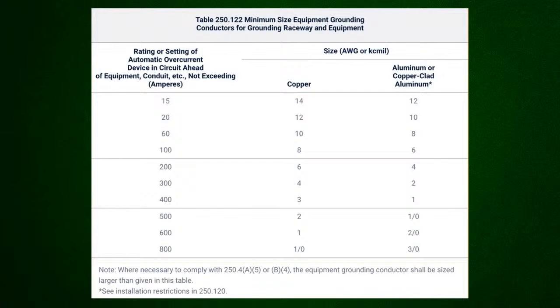Because when I do the ungrounded phase conductors and the neutrals, they're all sized based on the calculated load. The equipment ground is not based on the calculated load. It has nothing to do with it. All it has to do with is the fault current path back based on the size of the overcurrent protection device. So if I took, and let's just say it was 800 amps and I paralleled 3/0 over there, guess what? I need a 3/0 in each one of those for the equipment ground. And that takes care of the fault current path back based on the size of the overcurrent protection device. And the thing is, it doesn't matter if it's in parallel or if it's a single run. It doesn't matter about the circular mills.